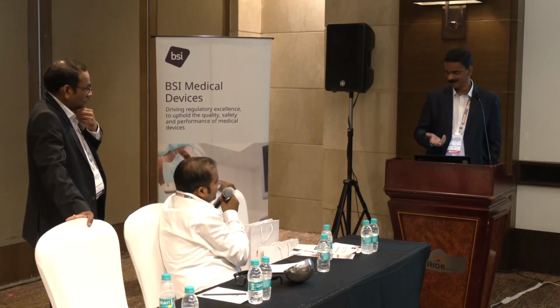There is the case of a legacy device. Then we have to go to MDCG 2020-6. It says you can demonstrate this. So when somebody does not accept it, you can quote MDCG 2020-6. MDCG is not a legally binding document, but it is a guidance document issued by the EU Commission itself. Since there are no other harmonized standards or explanations available, the manufacturer can justify. As a BSI reviewer, we will accept that.